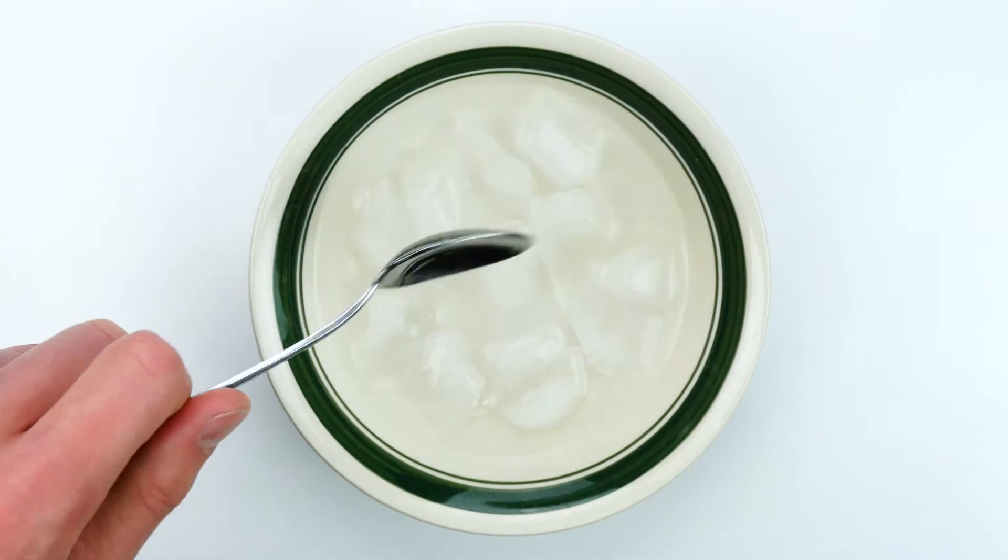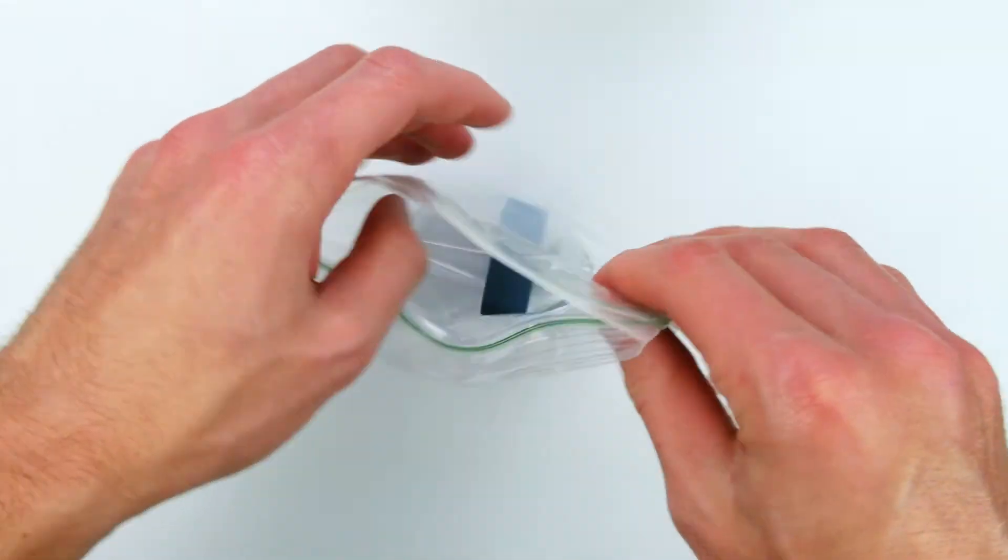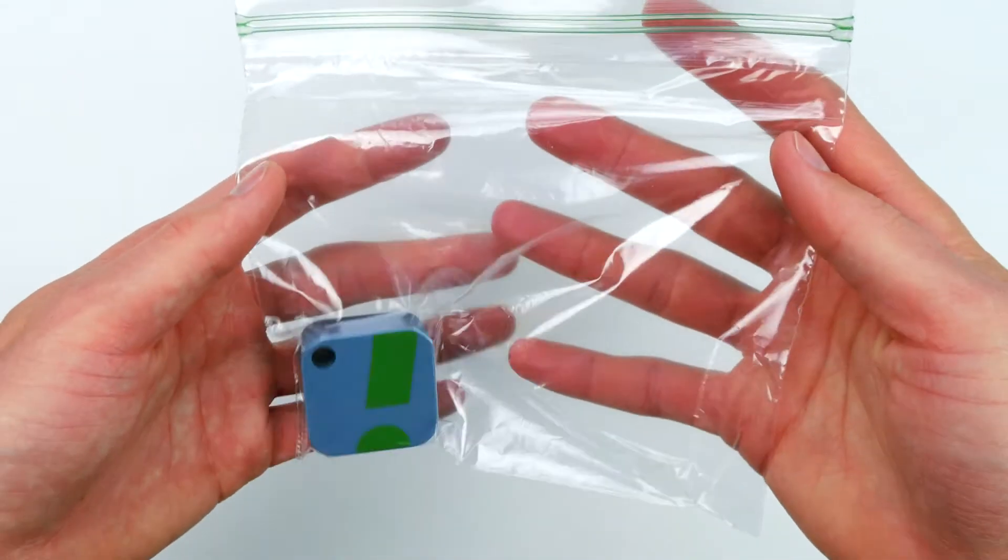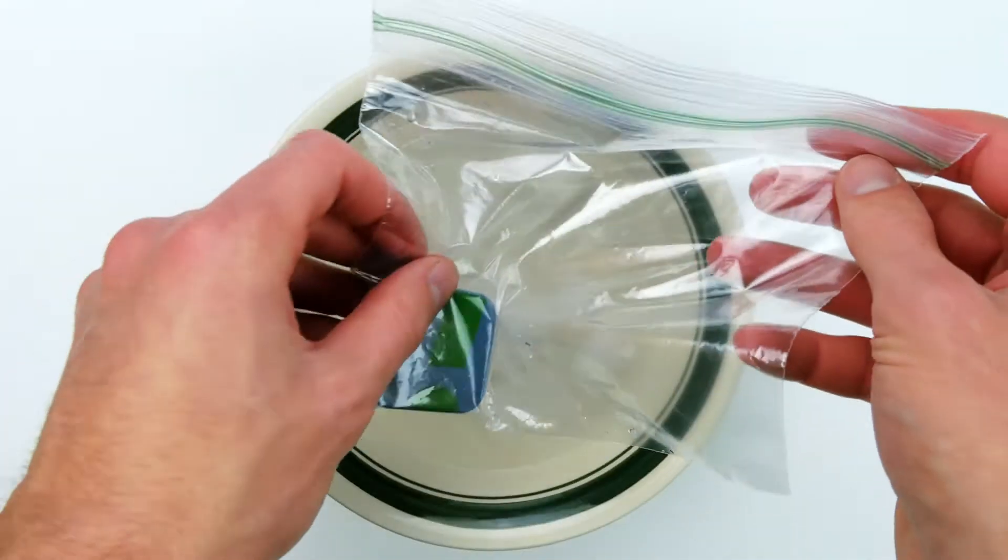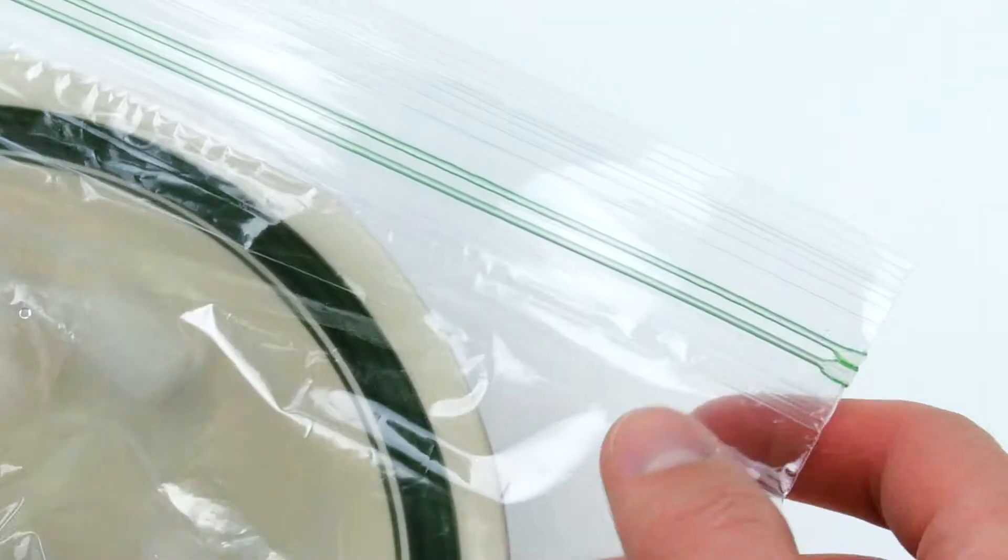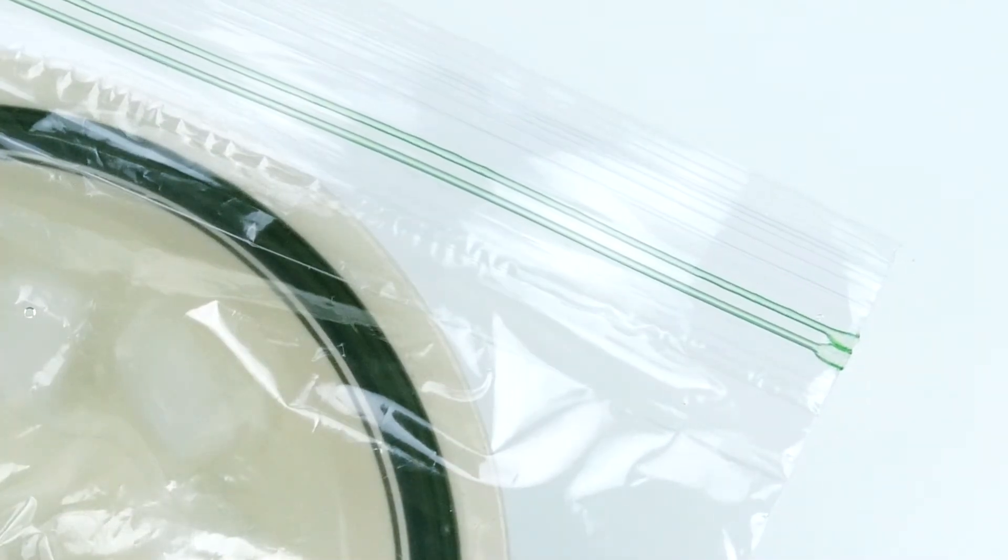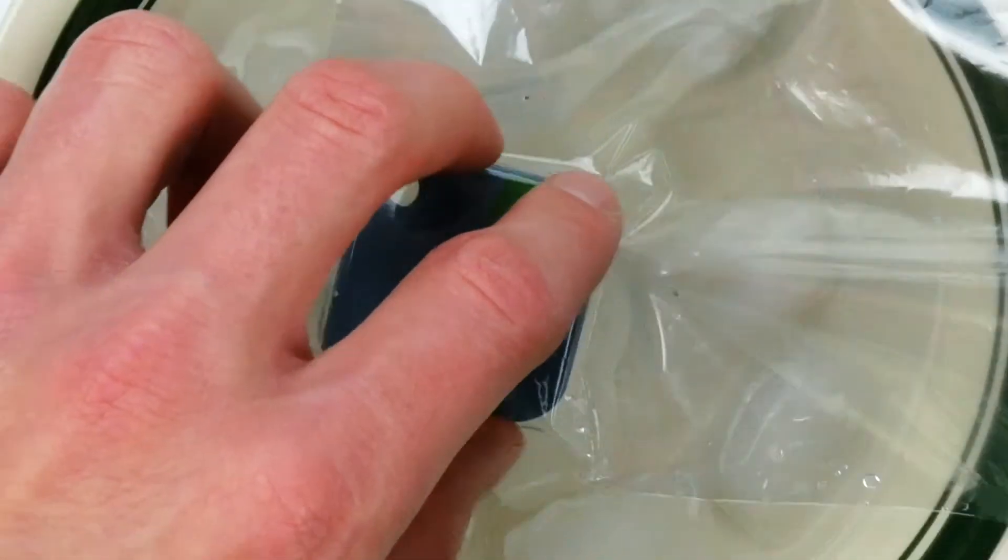Stir the ice and water mixture and let it sit while you seal your SensorPush in a zip-top baggie. Get as much air out of the bag as possible. Place the baggie with the SensorPush in the water. It's best to keep the zipper out of the water, just in case it doesn't seal properly.